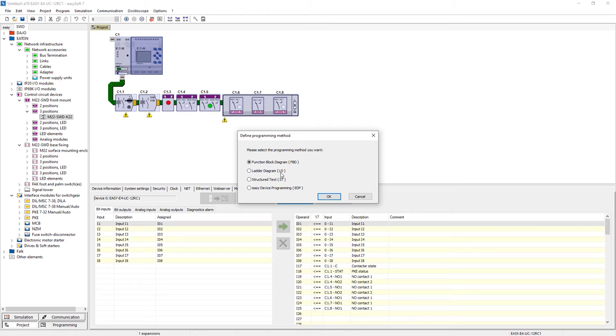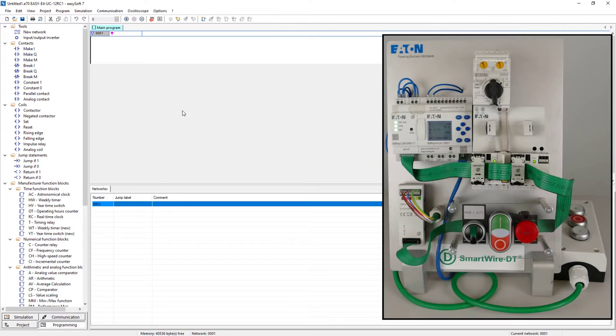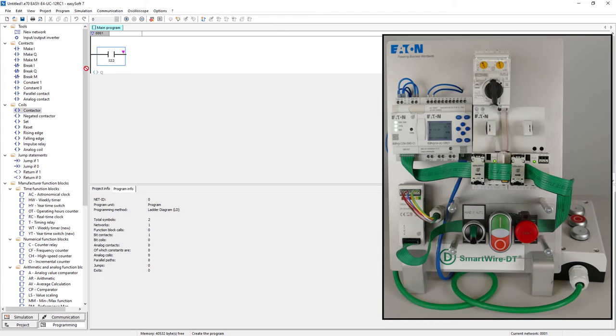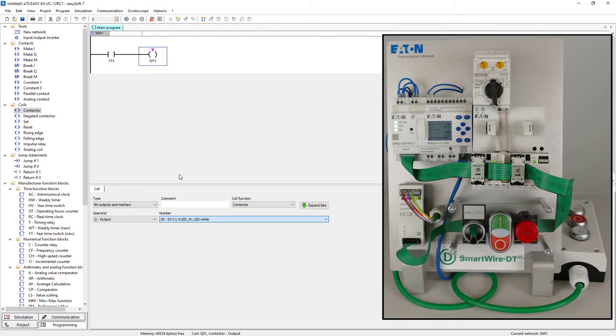For a short example program the ladder diagram is selected as programming language. Here the left contactor has to be switched on and off via the manual auto selector switch in the manual position. The manual setting is indicated by the white indicator light between the green on and red off buttons. Only in this position it is possible to switch the left contactor on and off. If the selector switch should be set to the zero position again when the contactor is switched on, the contactor should be switched off.